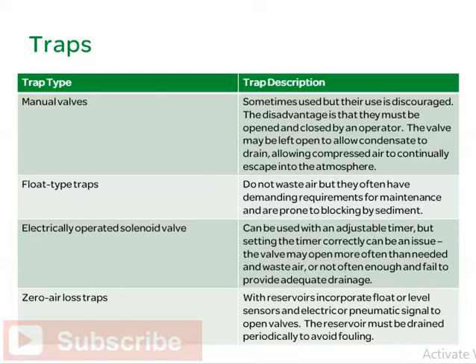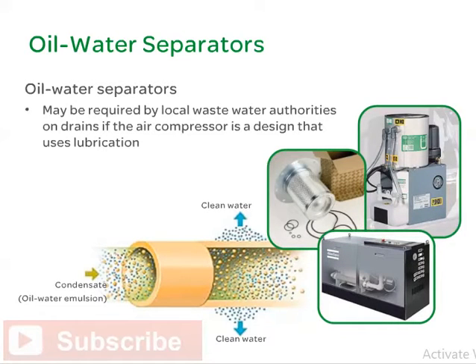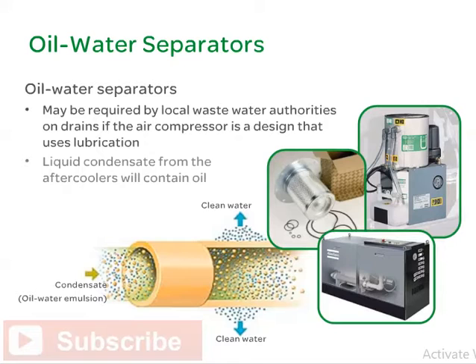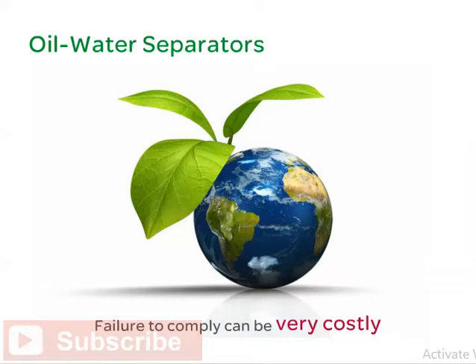Zero air loss traps with reservoirs incorporate float or level sensors, and electric or pneumatic signals to open valves. The reservoir must be drained periodically to avoid fouling. Oil water separators may be required by local wastewater authorities on drains if the air compressor is a design that uses lubrication. The liquid condensate from the after coolers will also contain oil. Most countries have laws that forbid dumping this oily water on the ground, into waterways, or into sewers. Failing to comply with these requirements can be very costly.